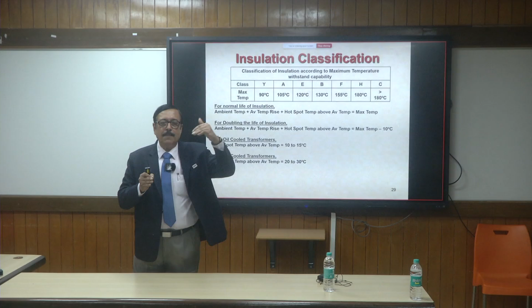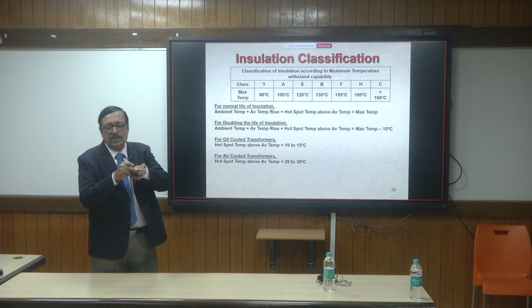Suppose I take class F 155 and I permit the hotspot to go up to 155. In a recent failure analysis, I proved to them this is going to happen because they are not taking into account the hotspot temperature. So it will fail. The hotspot will be much higher, and over a short period of time, the insulation will lose its characteristic and windings will touch together and things will become a short circuit altogether. So you have to take into account the class of insulation.